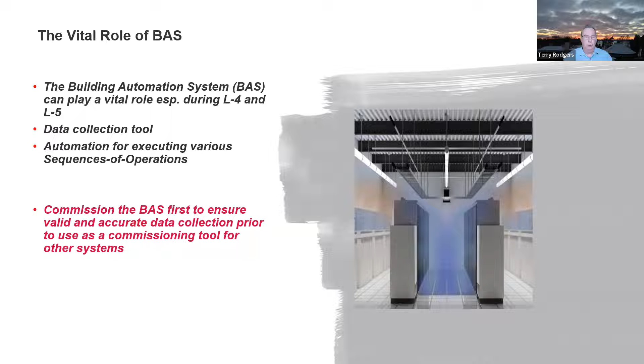So the BAS system is absolutely critical to the commissioning of any building. The building automation system is critical because it actually controls the infrastructure. So especially during the level 4 and level 5 testing, the functional performance testing, we need the BAS system to execute the logic and the sequence of operations, but it's also a data collection tool. We use it to read the responses, the stability of systems to maintain conditions, etc. So it's critical. But that also means we need to commission the BAS first, prove that it's functioning correctly and that it's accurate and reliable before we use it as a commissioning tool, including executing sequence of operations or relying on the data that it collects.